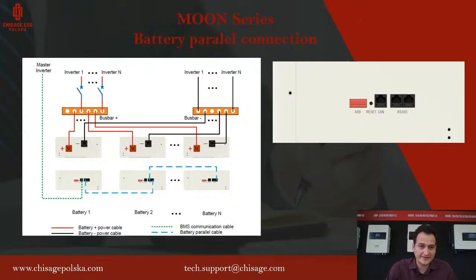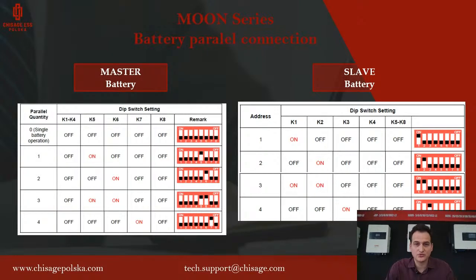And if we connect this correctly, then we have to set the DIP switches correctly. On the master, on the left, we pick how many batteries we connect in parallel. So if we have two batteries, switch number 6 will be on, all the others off. If we have 3 batteries, numbers 5 and 6. If we have 4, number 7. All the others are in our user manual. So I just pick here these 4.